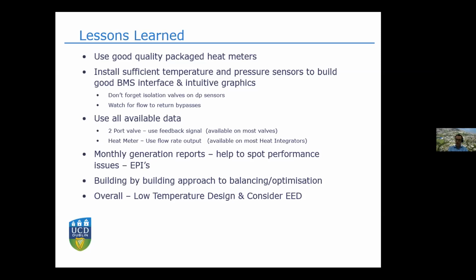This is a real bugbear of mine: you put something in to allow you to commission the system easily on day one, but if something goes wrong, it poses a risk to mixing and to the operation of the system for the next 20 or 30 years. So we like really good justification for putting in bypasses or anything that could go wrong and drag down your system, like putting in two valves instead of one and hoping both stay working.